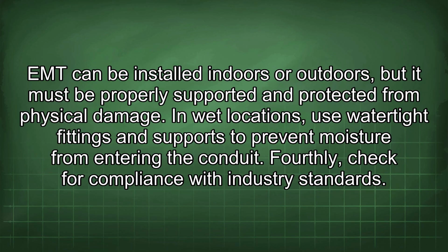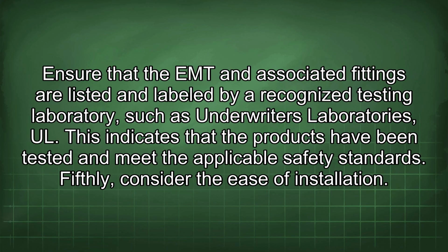EMT can be installed indoors or outdoors, but it must be properly supported and protected from physical damage. In wet locations, use watertight fittings and supports to prevent moisture from entering the conduit. Fourthly, check for compliance with industry standards. Ensure that the EMT and associated fittings are listed and labeled by a recognized testing laboratory such as Underwriters Laboratories, UL. This indicates that the products have been tested and meet the applicable safety standards.